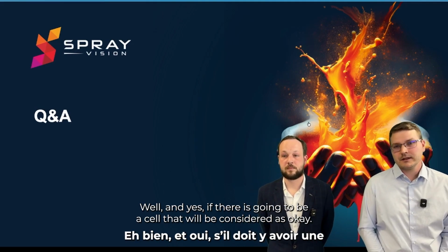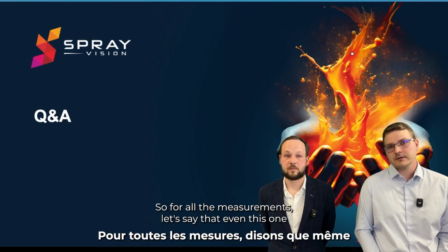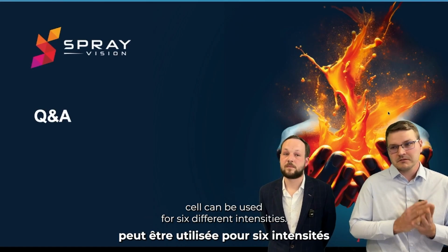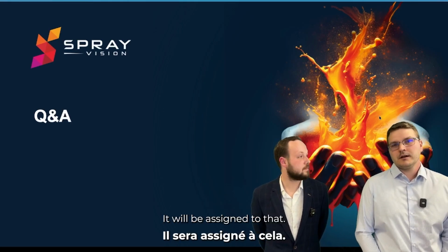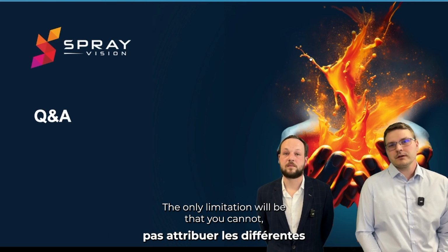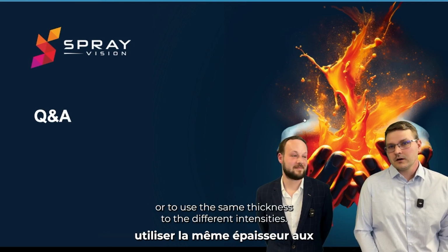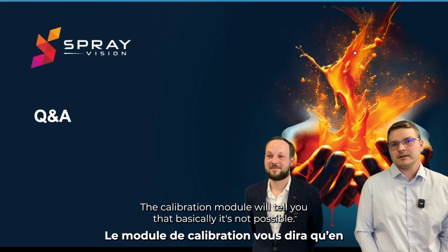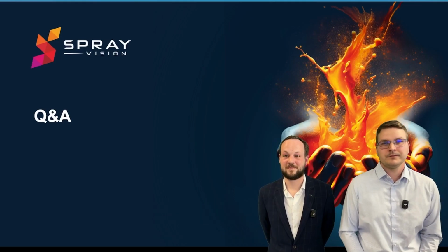And yes, if there is a cell that will be considered an OK cell for all the measurements, let's say even this one cell can be used for 6 different intensities, it will be assigned to that. The only limitation is that you cannot assign different thicknesses to the same intensity level, or use the same thickness for different intensities. The calibration module will tell you that it's not possible.